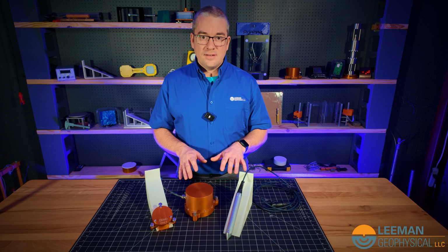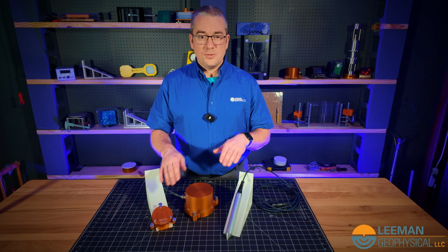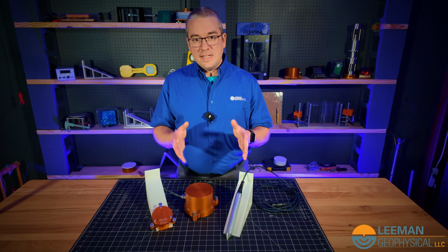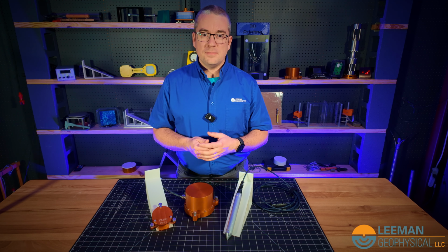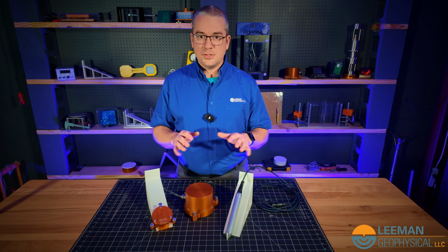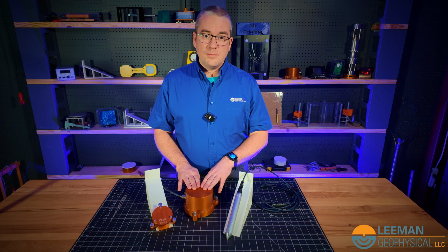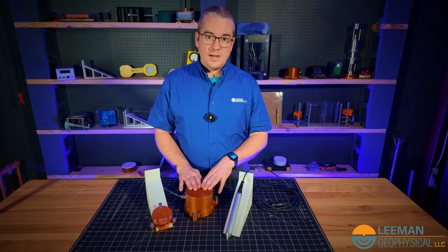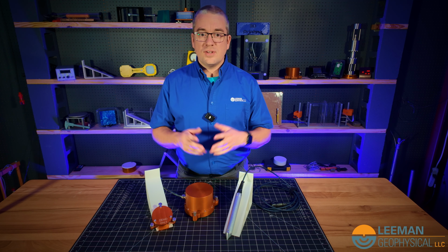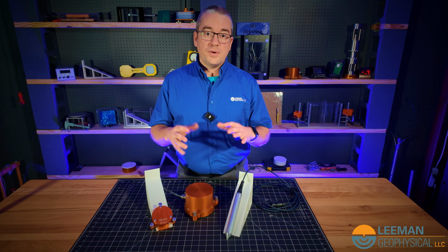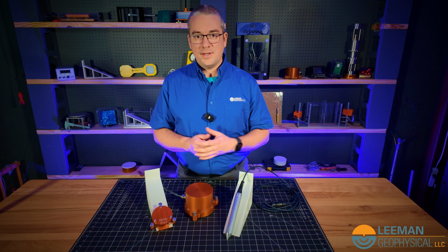Generally, we recommend for the MEMS instruments, which pull a lot less power, at least a 5 or 6 watt solar system. 10 is better if you're going to be out with long periods of potentially bad weather. Or for the PTM, we generally recommend a 20 watt solar system for deployment. Now, we've got a lot more information in other videos on how to calculate the appropriate solar panel for your setup, so we're not going to go into that here.